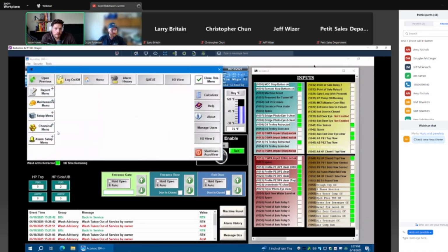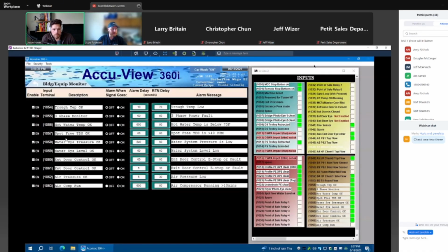So, yeah, a brownout, for those who don't know, is three-phase power. If you lose any one or two legs, but not all three. A blackout is all three. A brownout would be single phasing, losing one of your three phases. If that happened and you had the three-phase monitor equipment installed, that three-phase monitor detects any low voltage, high voltage, or any phase loss. When that monitor detected it, it would change its state, and you would get an alarm via the same alarms, email, or phone that you did your other alarms.